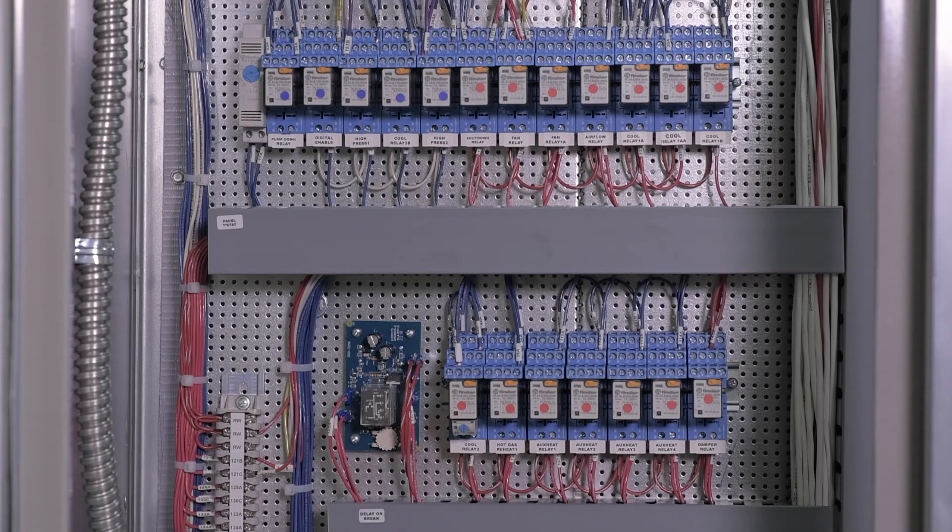The circuit board with the relay and the dial is a delay on break timer. We use it when the controller stops calling for the fan. It allows us to keep our supply blower on for three minutes to help cool down the heat exchanger.